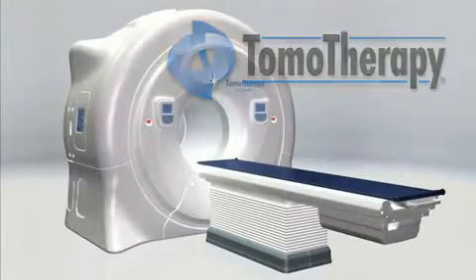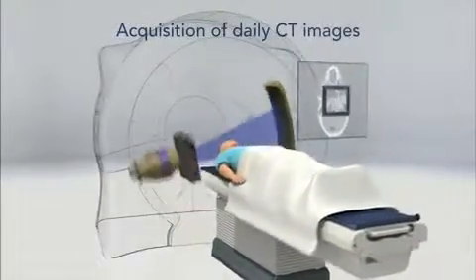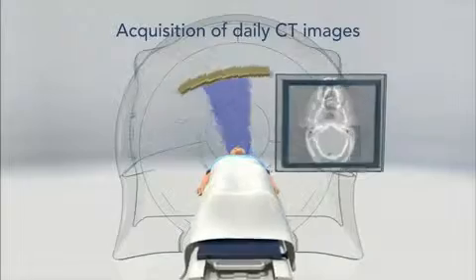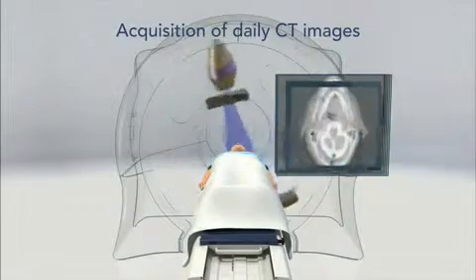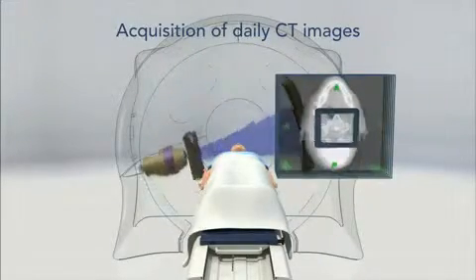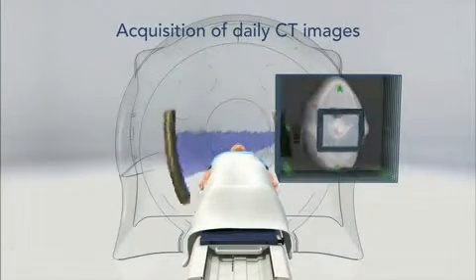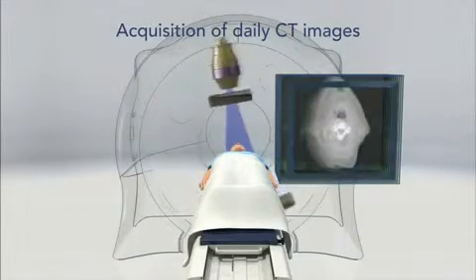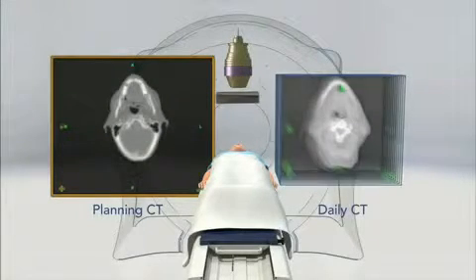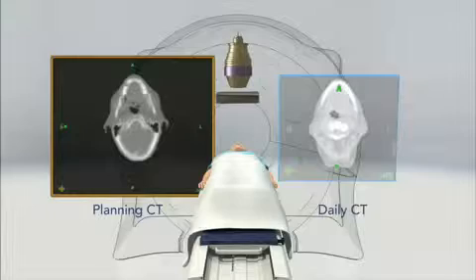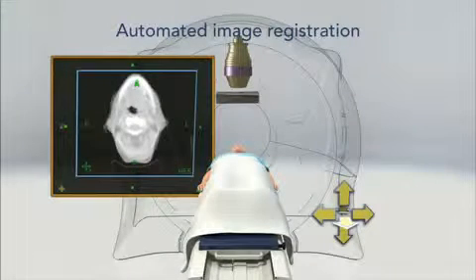The session begins with patient positioning, based on a 3D megavoltage CT image acquired from the same X-ray source that will later be used to treat the patient. As with a diagnostic CT scanner, our system uses a rotating, narrow fan beam of X-rays where the source moves in a helical pattern around the patient. With our high-efficiency X-ray detector, a 3D image of the patient is produced with a very low dose, typically only 1 to 2 centigray. The megavoltage CT image is automatically aligned with the CT image used for treatment planning. This step determines a 3D shift required to precisely position the patient for treatment.